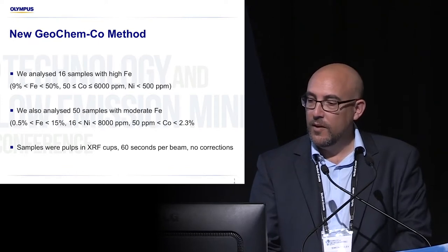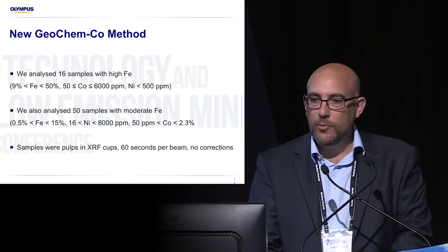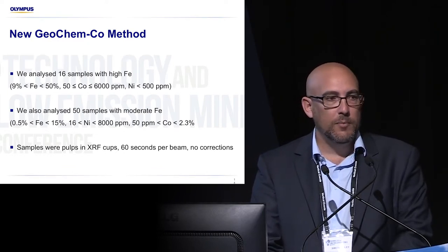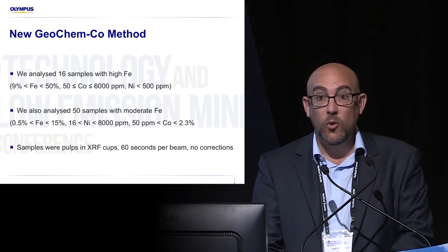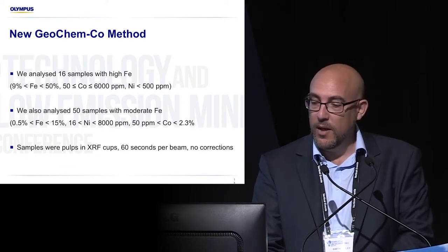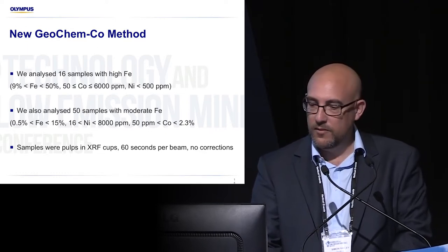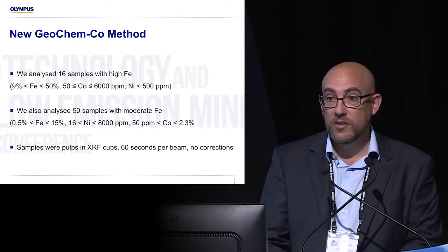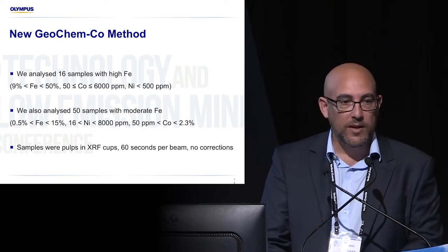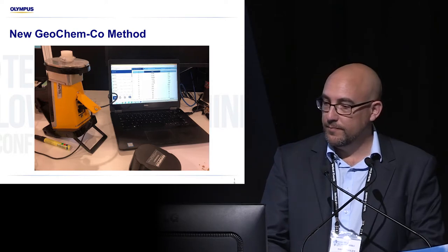So does it work? I approached two companies. One company had 50 samples that they'd used to proof principle on another handheld XRF brand — that brand had promised them the ability to see cobalt when iron and nickel were present and it didn't work. I also analysed another set of 16 samples with significantly high iron, really putting the algorithm to the test. The samples were pulverised samples back from the lab, put in XRF cups and analysed at 60 seconds per beam. No corrections were made and no tweaking of the data.